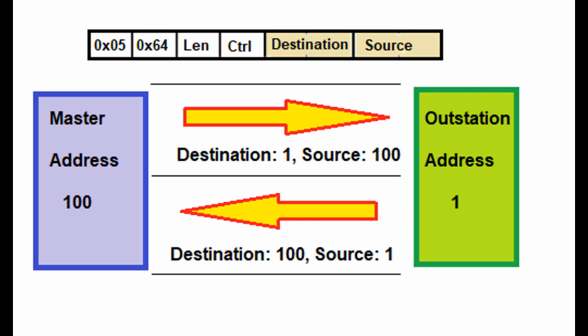Many systems do not require a master address. For these, outstations either do not validate the master address field or commonly assume it to be 0. Some systems do require a master address. If basic communication is failing, then the master address setting is a good place to look for a configuration issue.